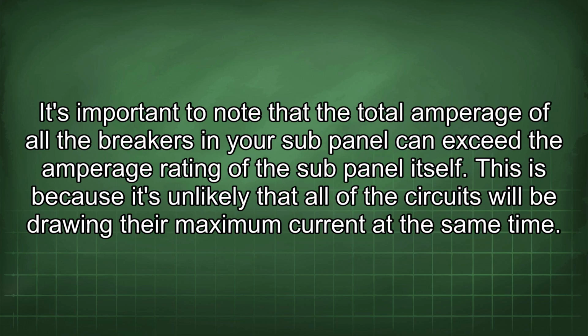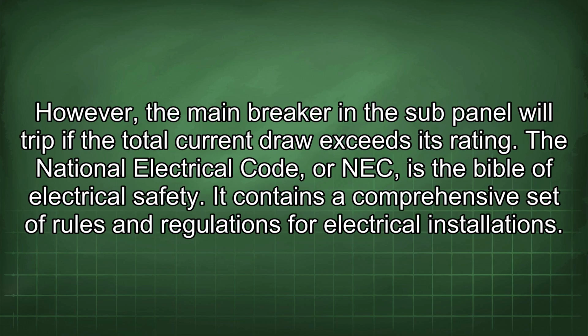It's important to note that the total amperage of all the breakers in your sub-panel can exceed the amperage rating of the sub-panel itself. This is because it's unlikely that all of the circuits will be drawing their maximum current at the same time. However, the main breaker in the sub-panel will trip if the total current draw exceeds its rating. The National Electrical Code, or NEC, is the Bible of electrical safety.